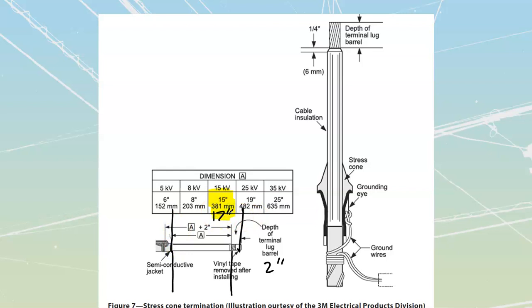Once I get the 17 inches of cable stripped back, I'm then going to strip back the actual insulation 2 inches, and tape over the ends so I don't accidentally bend or flare them. Then I'll go another 2 inches past that and pull back any ground conductor on the outside of my cable. A lot of these have not just the insulation shield or semicon, but also a wrapped grounded conductor around the outside.